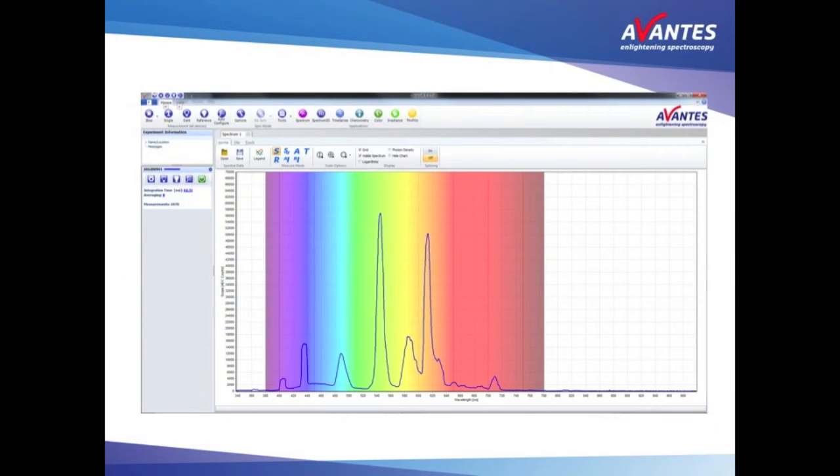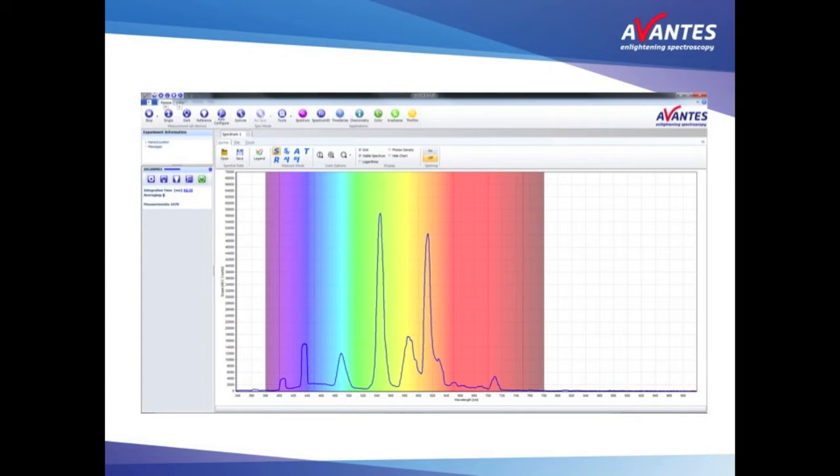Using a spectrometer in scope mode gives you spectral information regarding the light measured. However, in scope mode this is uncorrected raw data. Spectrally this data is correct, but on the intensity axis the information is not weighted.